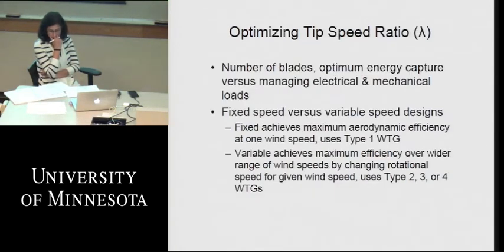So the first bit of control is optimizing the tip speed ratio. The coefficient of performance, that CP I've been talking about, the maximum energy extraction from the wind, is based on these 2 components, the tip speed ratio and the pitch angle of the blade. Fewer blades gives you a higher tip speed ratio, a higher lambda, and in doing so gives you the opportunity for the optimum energy capture, in contrast to the necessity for managing these electrical and mechanical loads on the tower and on the output power as such.